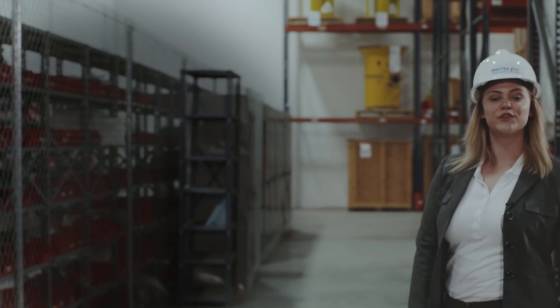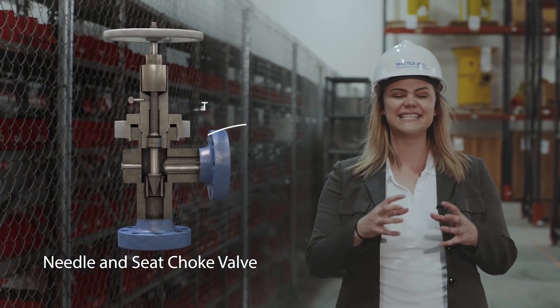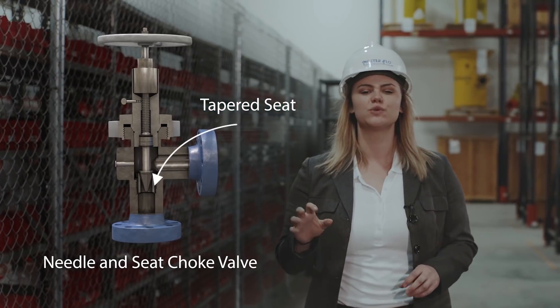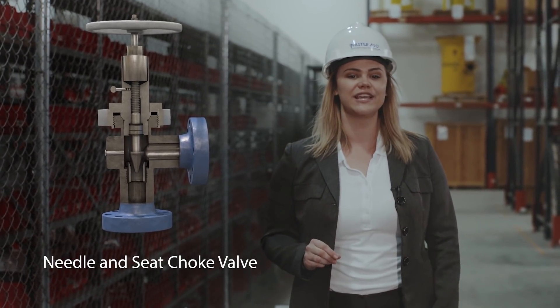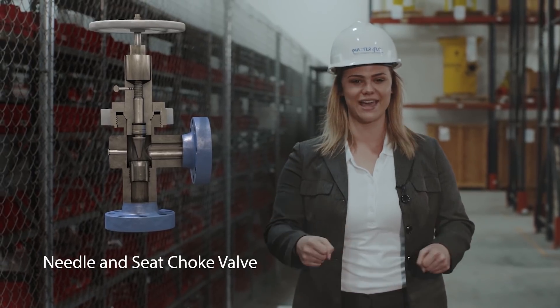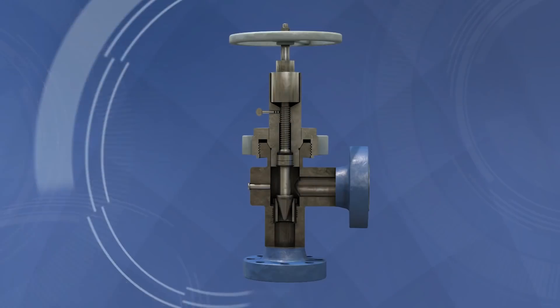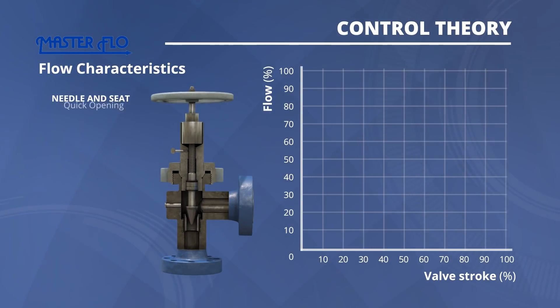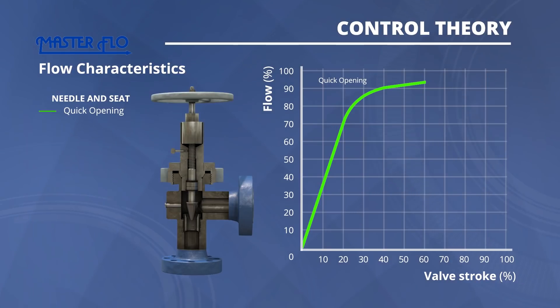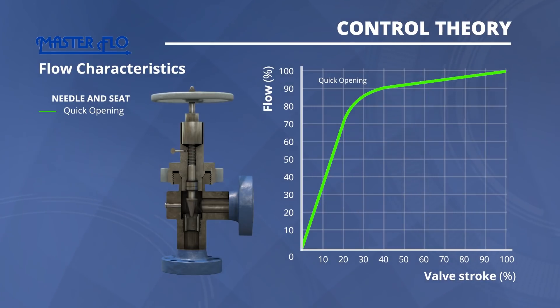Let's discuss the flow characteristics of four types of choke valves. The needle and seat has a tapered lead on its stem to restrict the opening by closing the tapered seat. The throttling is achieved by rotating the handle on its rising stem. Due to the tapered design, a small rotation of the stem handle can cause a significant change to the orifice opening. This choke design doesn't provide a high degree of control — when the choke is open halfway, you experience full flow, losing most of your control.